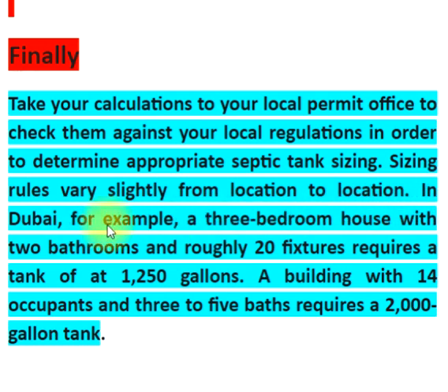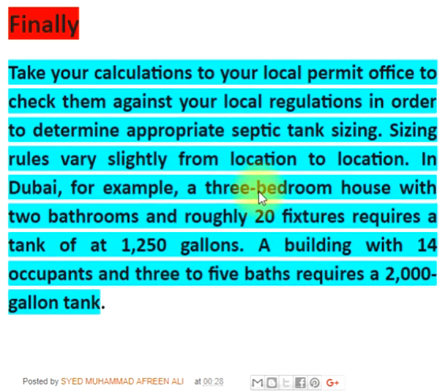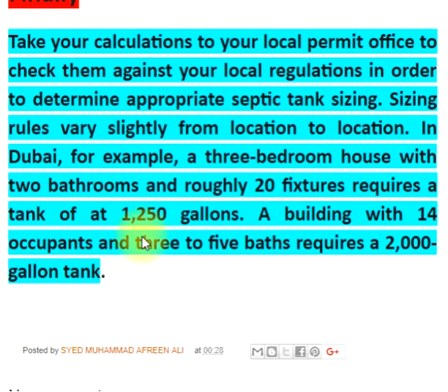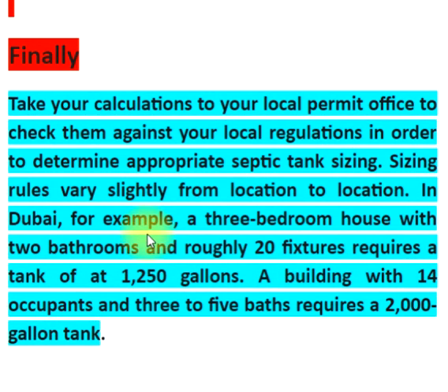In Dubai, for example, a three-bedroom house with two bathrooms and roughly 20 fixtures requires a tank of 1,250 gallons. A building with 14 occupants and three to five baths requires a 2,000-gallon tank.